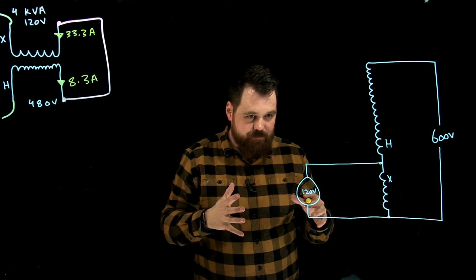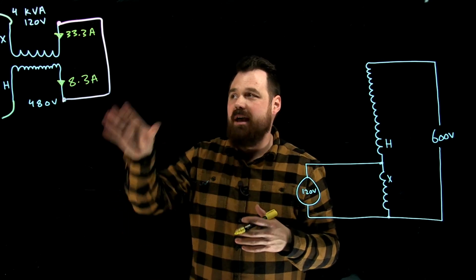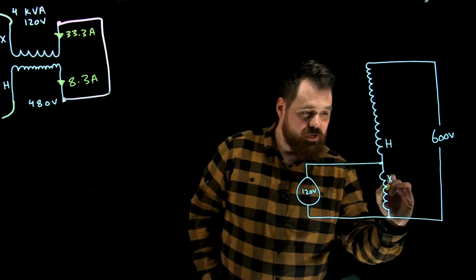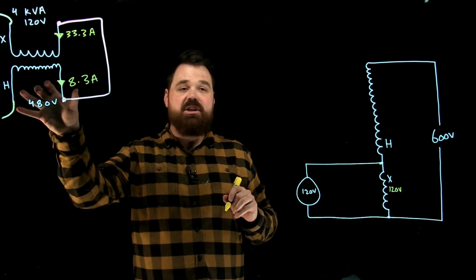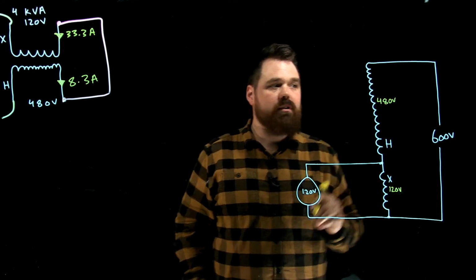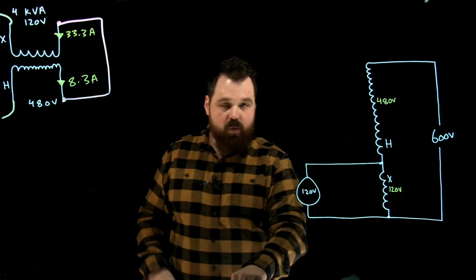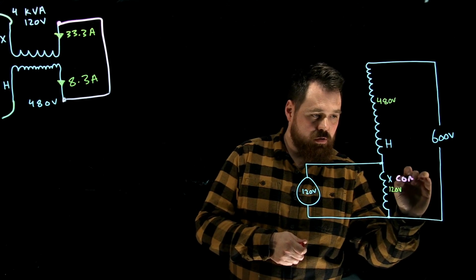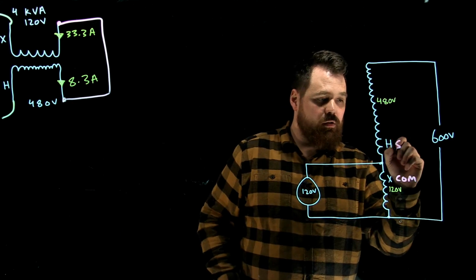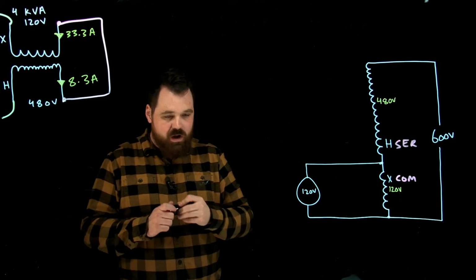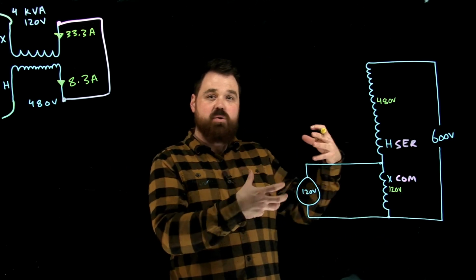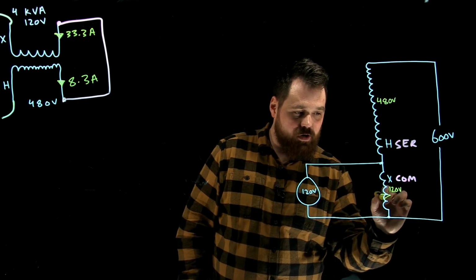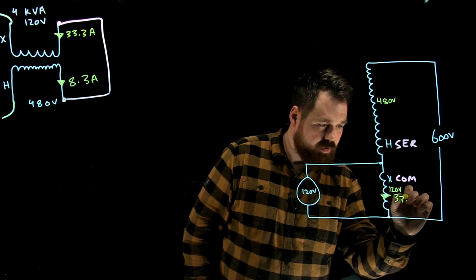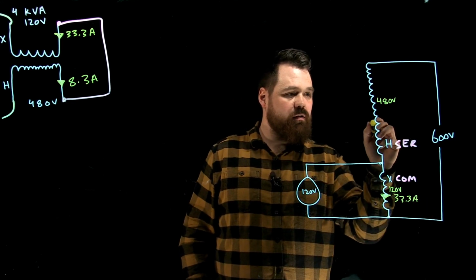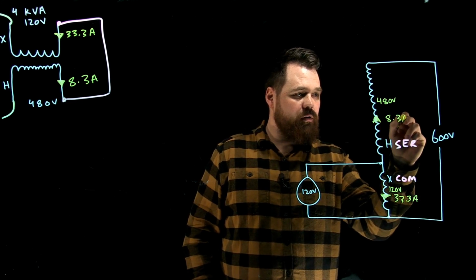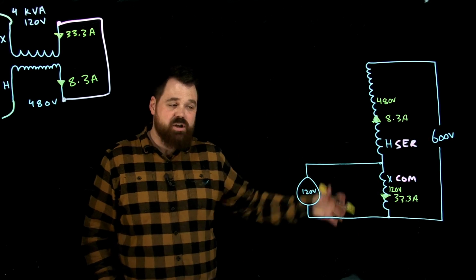Anyways, the winding ratings don't change, right? My X winding is still rated for 120 volts. My H winding, still 480 volts. Those ratings don't change. Now, what happened is our X winding became the common winding. My H winding became the series winding. What also didn't change, though, is the current that those windings can handle. So on my X winding, I can still have 33.3 amps. On my H winding, I still have 8.3 amps. The rating of those windings doesn't change.